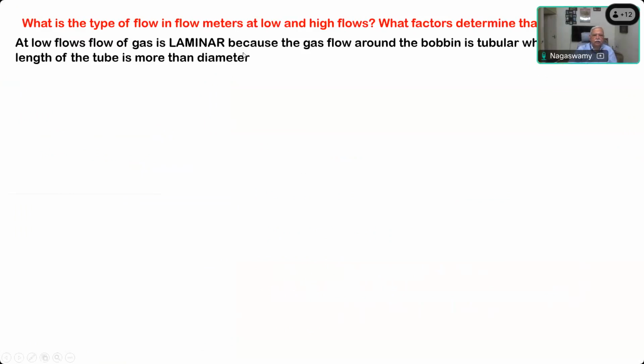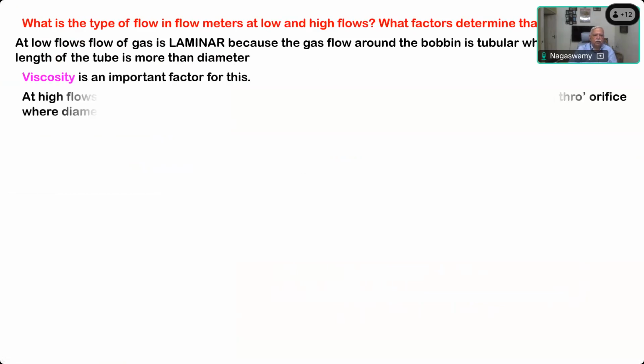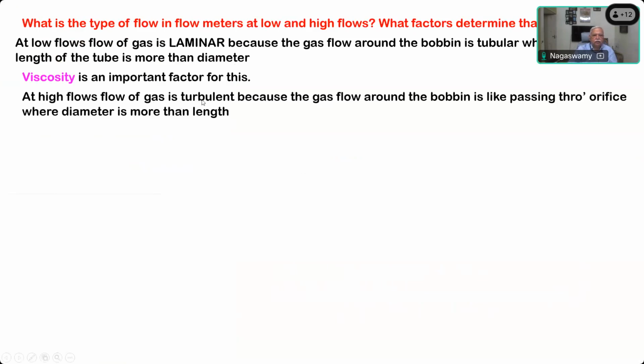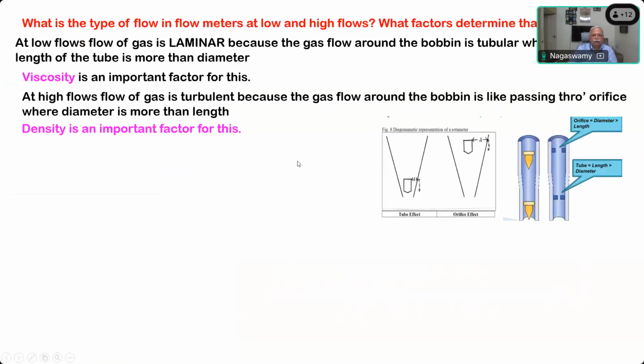At low flow, gas is laminar because the gas flows around the bobbin in a tubular space, where the length of the tube is more than the diameter, and viscosity is an important factor. At high flow, gas is turbulent because the gas flows around the bobbin through an orifice, where the diameter is more than the length, and density is an important factor. So this picture shows the tube effect and the orifice effect.